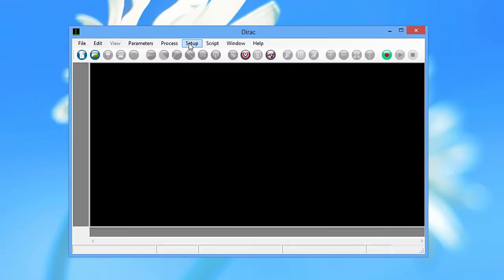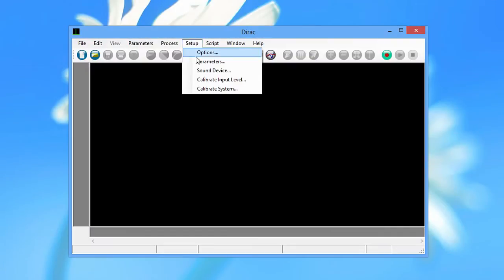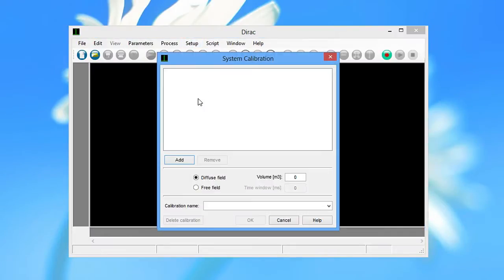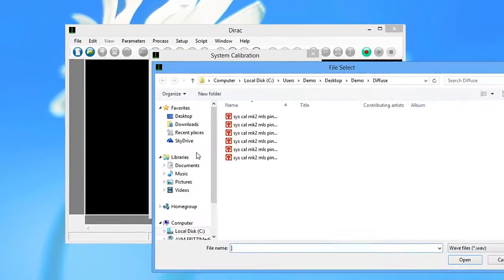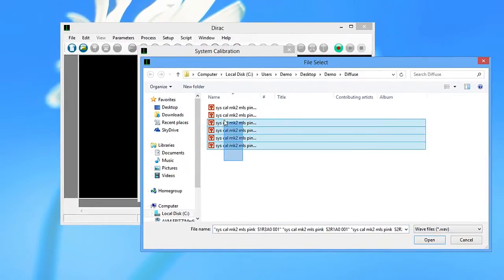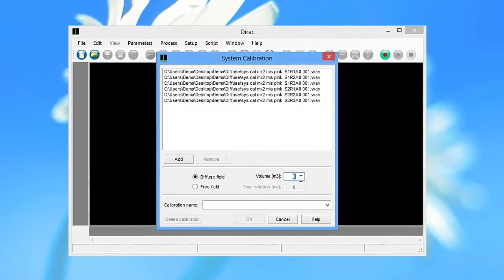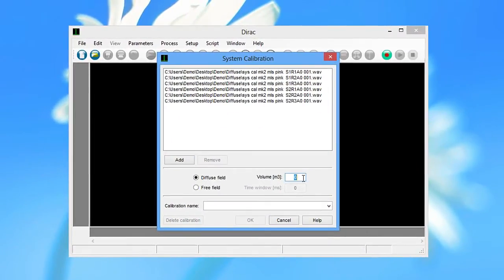Then, in Dirac, select Calibrate System. Select the system from the Setup menu and select the files you just measured. For reverberation chamber measurements, you select Diffuse Field and enter the chamber volume. Enter a descriptive calibration name and click OK.